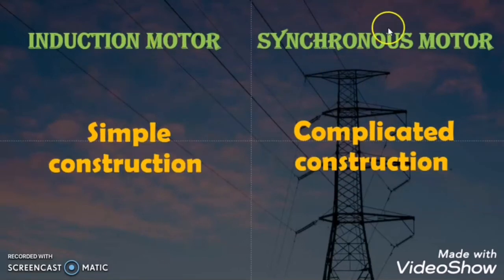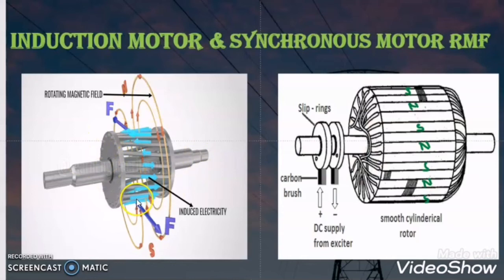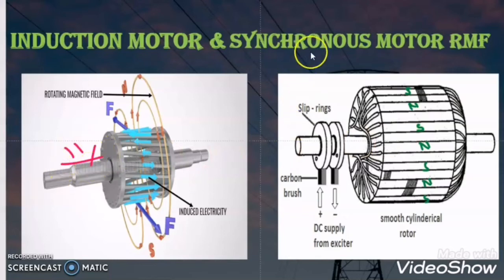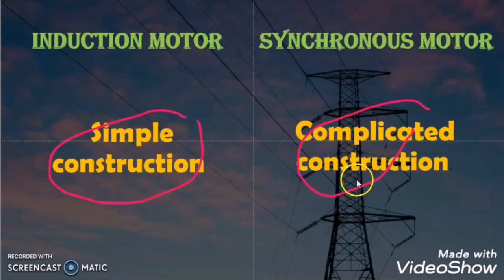The other difference is that the induction motor has simple construction but the synchronous motor has complicated construction. In the induction motor, the rotor is the simplest compared to the synchronous motor — no additional power supply is required, just rotor bars and end rings. But the synchronous motor requires power supply, slip ring and carbon brush arrangement, and windings. So the induction motor has the simplest construction while the synchronous motor has complicated construction.